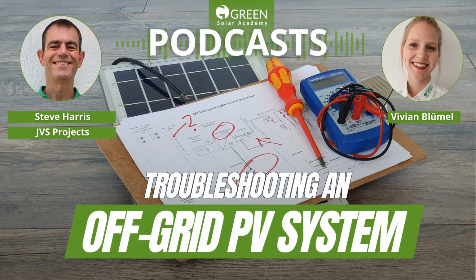And so you recommend that you should look around and take everything in the environment into account. One of the most common things I've found lately is people seem to be absolutely focused on these high output panels, these 400 watt 72 cell panels, and then they'll spend a chunk of money getting a bunch of panels, and then they will put in a very cheap PWM charge controller, and they don't understand that is going to limit the output of the panel dramatically, because you're pulling it to the system voltage.